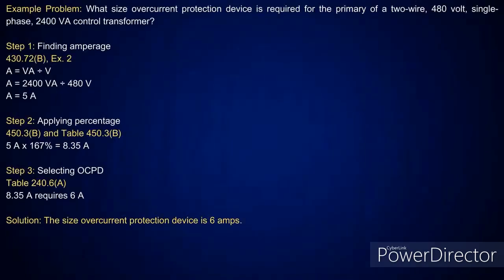Now this is where you're going to look at 430.72B exception 2. Now, this particular one, when you look at this exception, this is where you're on the primary side of a single phase transformer. And what it's going to tell you here is where you're going to be able to take this at 167%. So in 430.72B exception 2, it's going to tell you, basically, I need to determine my amperage.